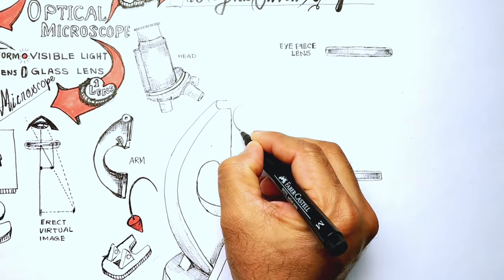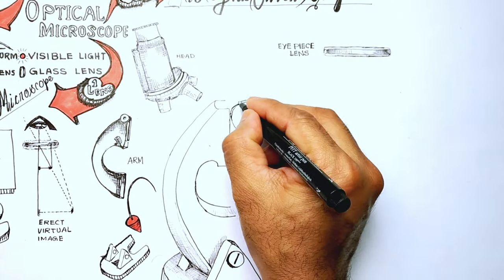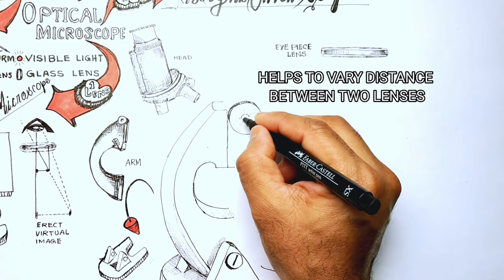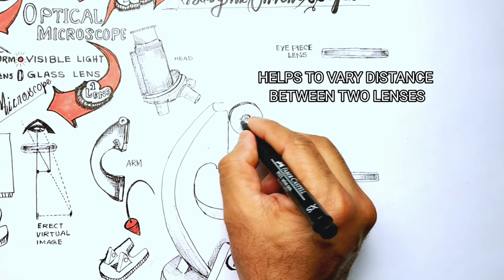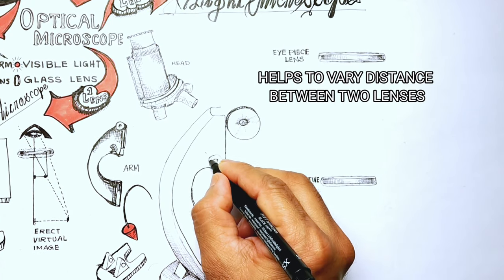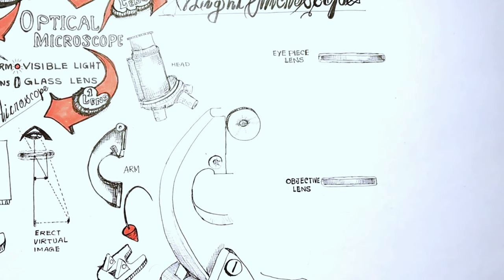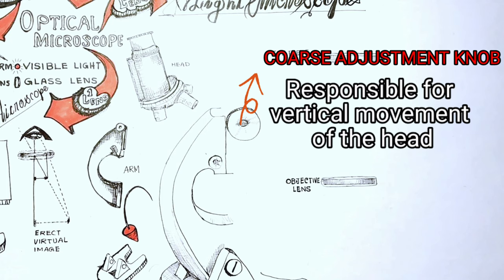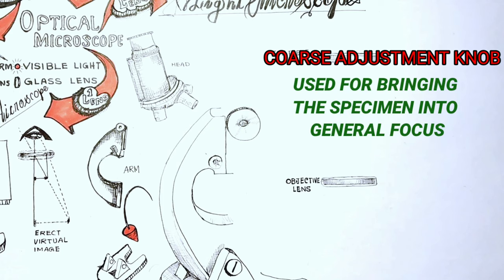There are two adjustment knobs located on the arm of the microscope. They are built on the same axis that allow the tubes to slide into one another, varying the distance between the lens and to bring the specimen into focus. The coarse adjustment knob located at the top of the arm moves the stage up and down. That produces a large vertical movement of the stage. This movement will help in bringing the specimen into general focus.